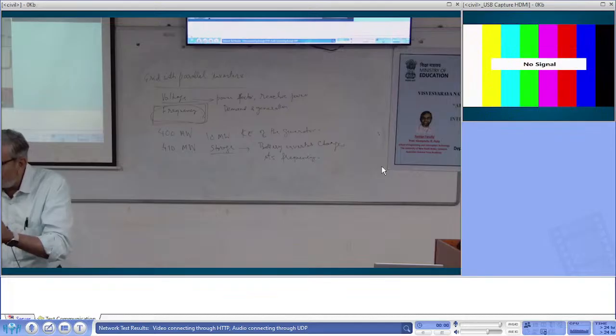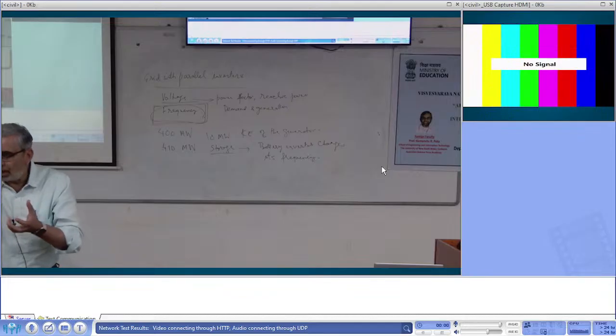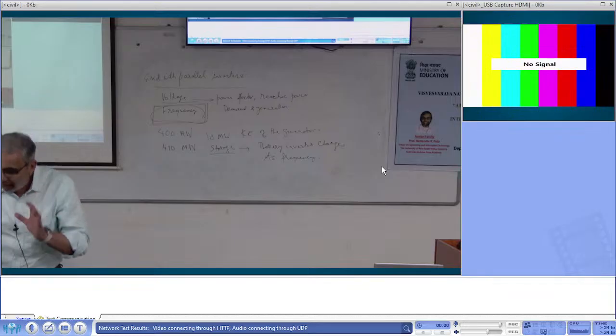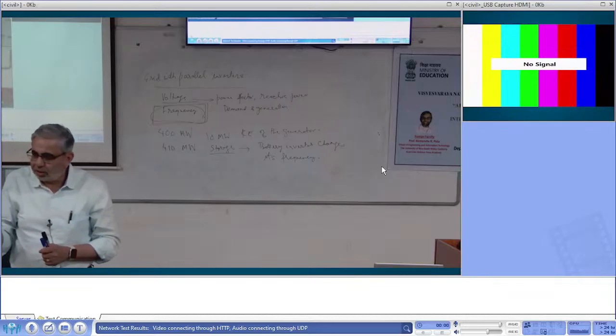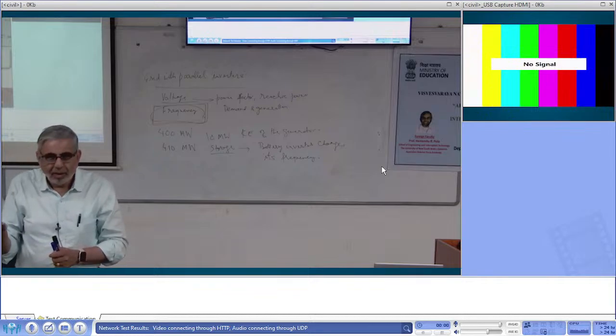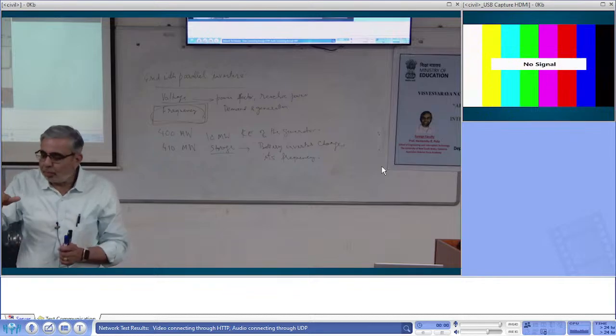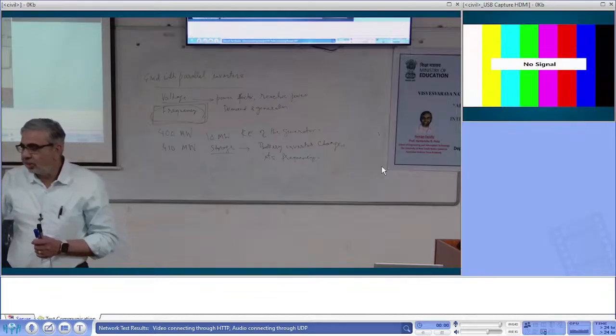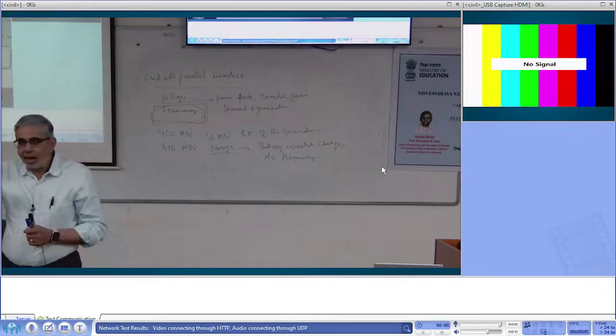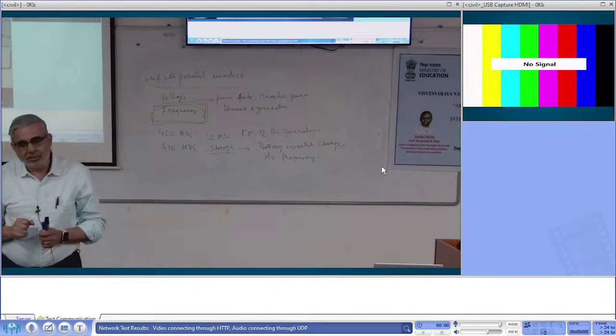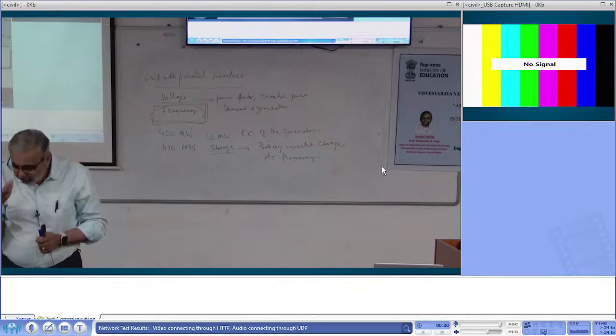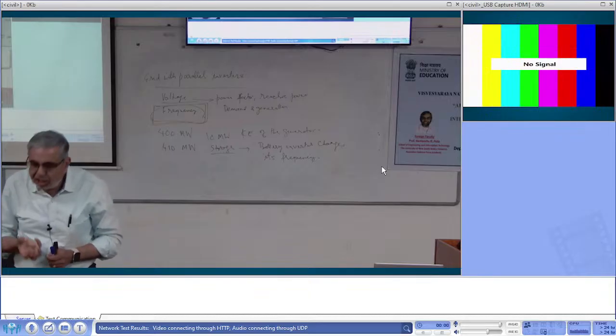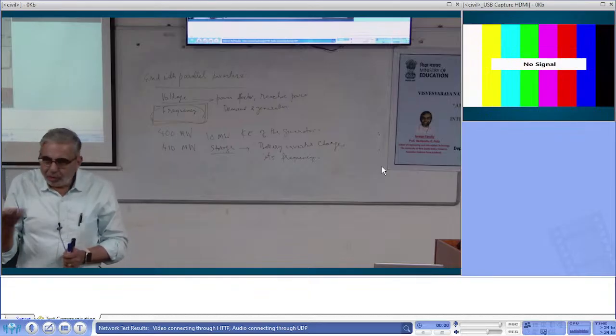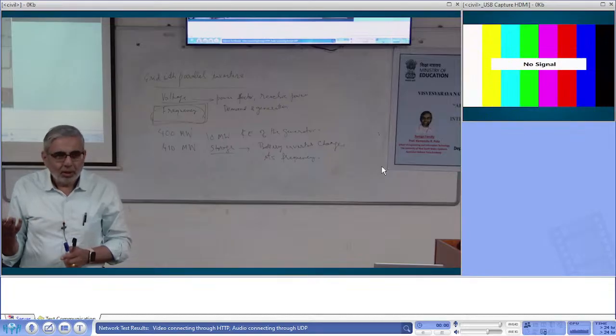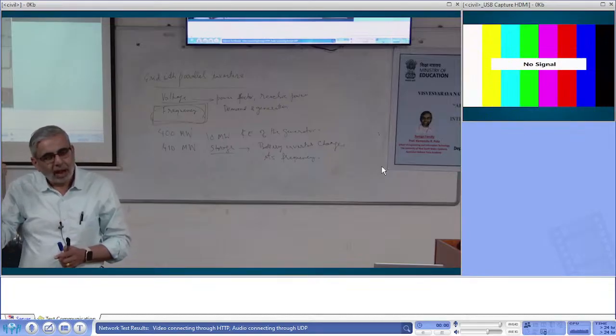But here that signal is not available. How is the battery going to tell that other inverter? Is the problem clear? So what the battery does is increase or decrease its frequency, proportional to how much power it is charging or discharging. The other inverters pick up that frequency, and by a pre-agreed scheme, those inverters change their output power so that the battery goes back to sleep.